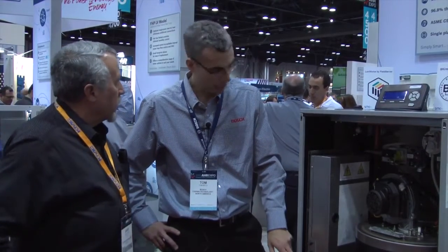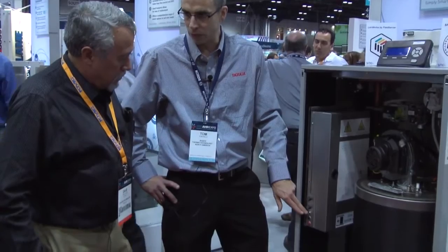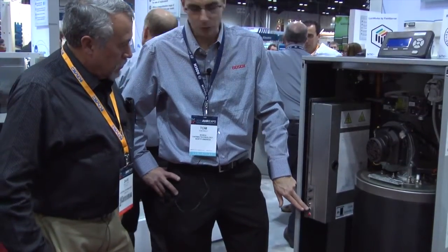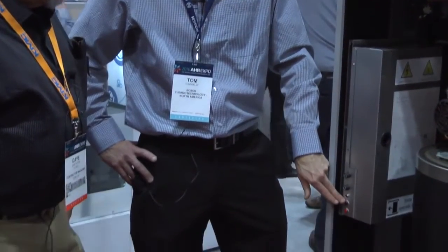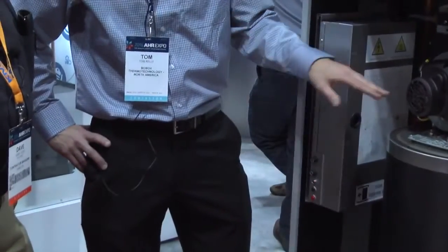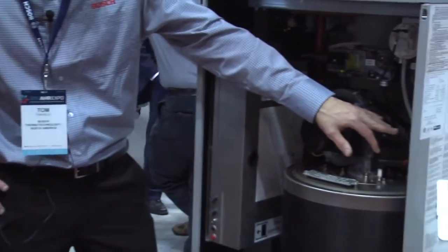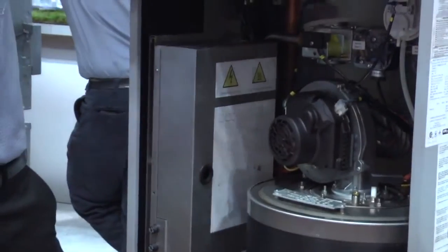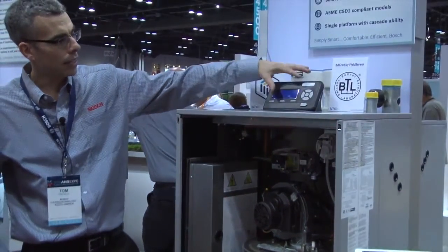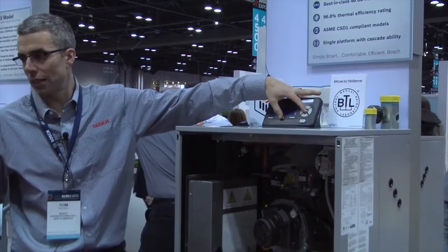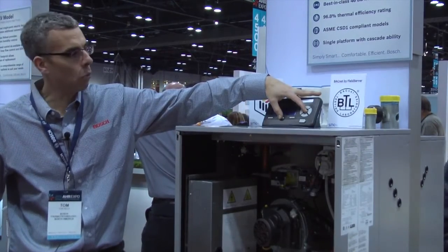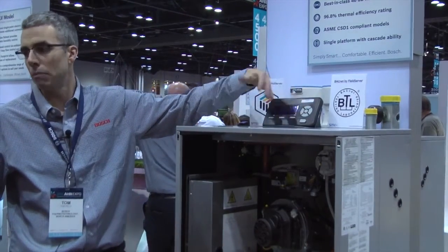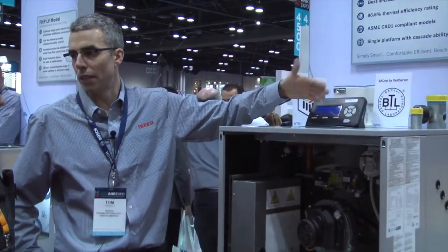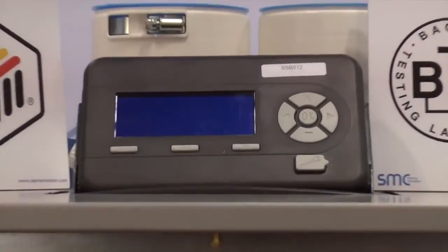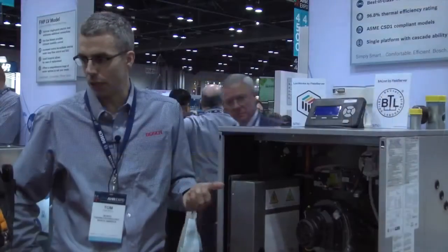Just like a ground fault interrupter circuit. Exactly. The LED will come on. When we hit the test button, it'll prove to the inspector that it's functioning. We can then hit reset to simply reset that low water cutoff. That's great. Now the other thing, on the manual reset high limit temperature sensor, we have that tied back to the control. So on the control, I can simply push two buttons simultaneously, hold for 10 seconds, and what will come up on the display is that I'm off on my manual reset high limit. So again, we can prove these sensors to an inspector, which are two crucial steps to an installation.